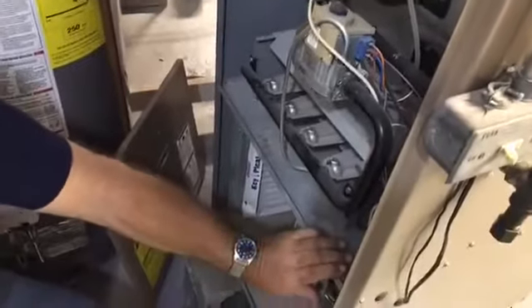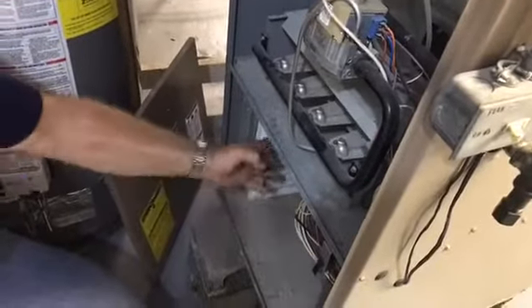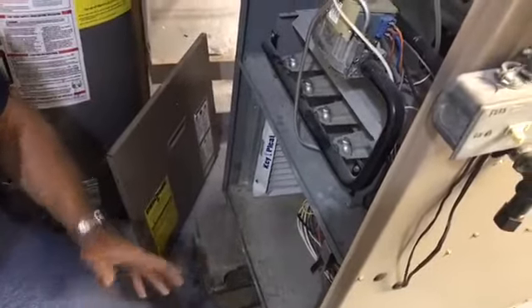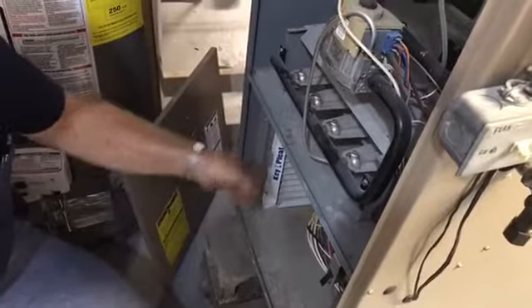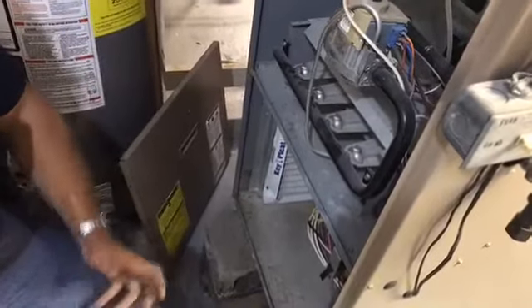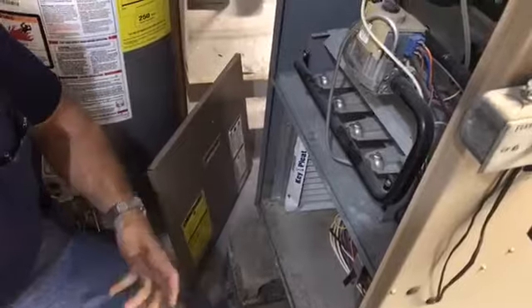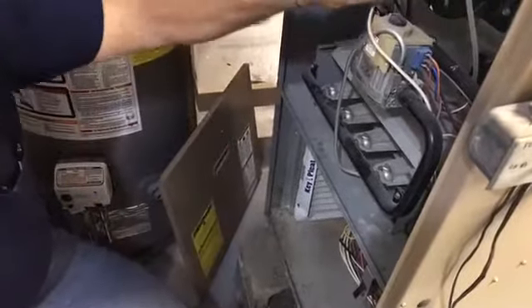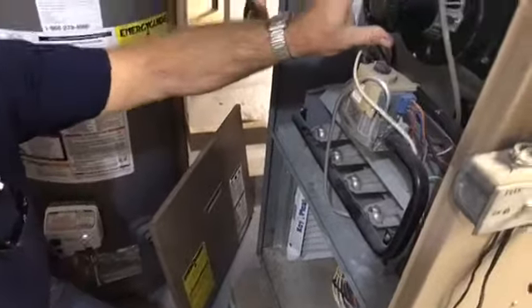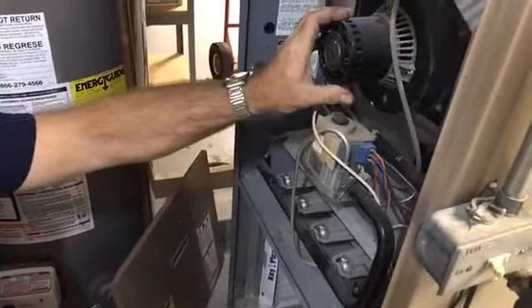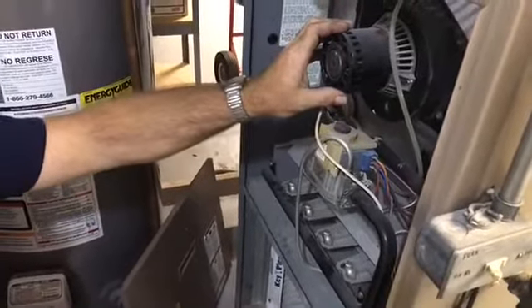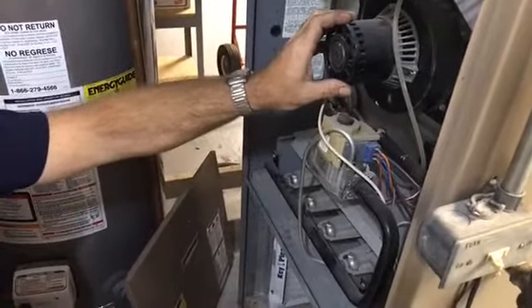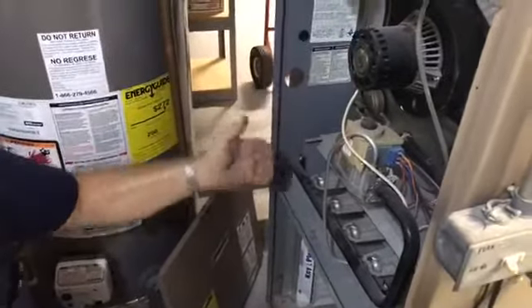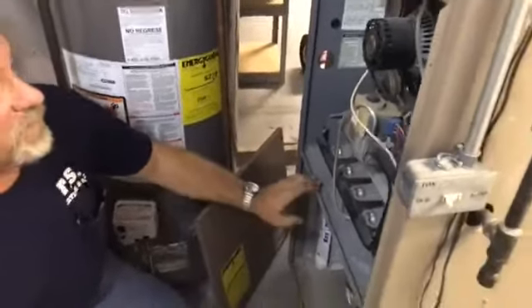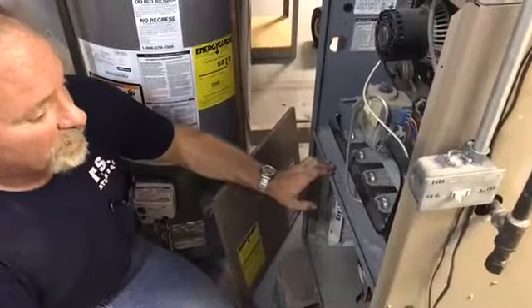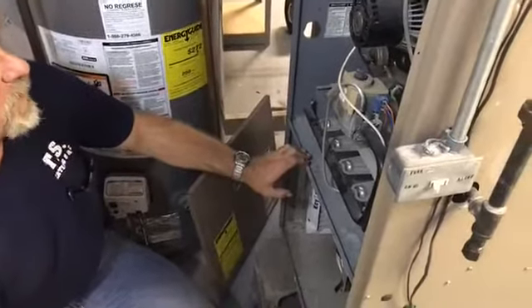Door safety switches, so you can't open the furnace up and stick your hand in while the fan's running. Yeah, that would be kind of a bad thing. Especially since your filter's inside. Normal things like that. This being an 80% furnace, we don't have issues with water and drainage like we do on the high efficiencies. High efficiencies produce water. We have condensate that has to be drained off, so we have drain tubing and things of that nature. But that's not present on this furnace.